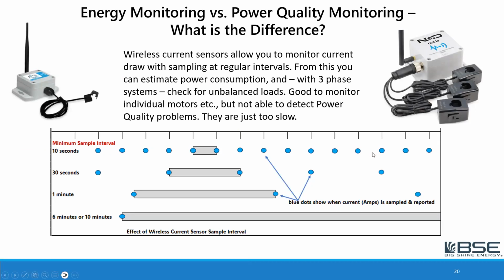I wanted to talk briefly about 2 different ways to meter power, and one is really for energy monitoring, and the other is for power quality monitoring. So there's two different types of devices used for that. Wireless current sensors are very handy devices, and they're very powerful. There's a lot you can do with them. So for example, you can put these throughout your facility and use them to monitor specific loads, and it will send a signal at a periodic interval to tell you how many amperes of current are being drawn. If you have a three-phase system and you want to make sure that all phases are balanced, you can use a three-phase version of that.